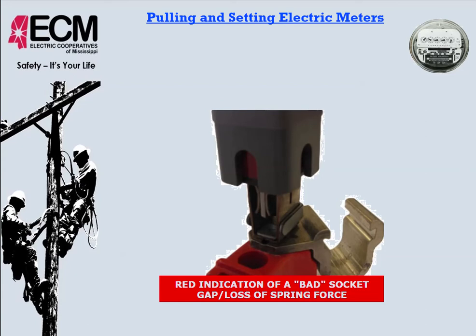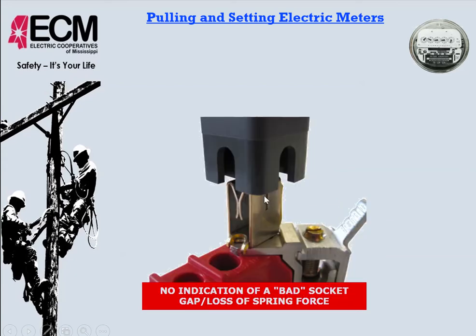What this device does is you actually take and push it into there, just like the meter would, and then when you pull out on it, you see that it shows a red color here, or it would show a green color there. If there's enough tension, it will pull a spring-loaded device in there out to the green part. If there's not enough tension, it will only pull it out to show the red part. So making sure that there's the proper tension before we set the meter is something that will help protect our equipment, such as the meter, and also maybe eliminate a trouble call somewhere down the road.